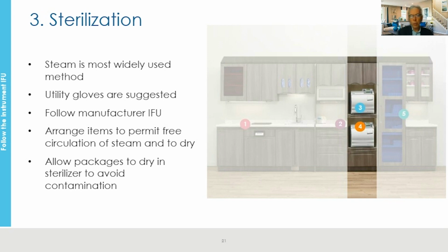It's really important to arrange the items you put in there - whether there are loose instruments or, if they're in a cassette, which again I prefer, that they're put in with racks and separators so you can get free circulation of steam. Also, when it comes time to dry, you can dry those instruments properly. And we always want to let that full cycle go through. We don't want wet instruments because, again, they're no longer sterile if that package tears.